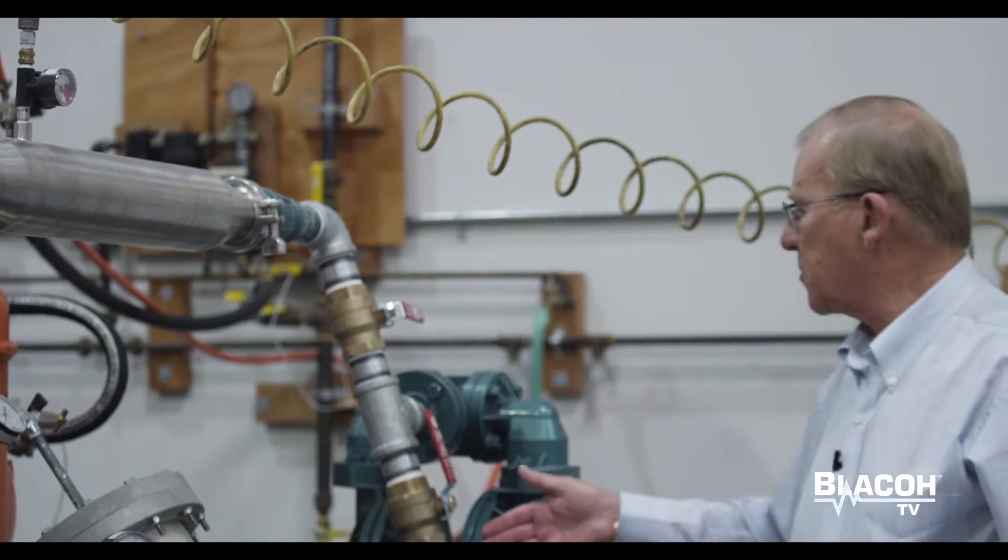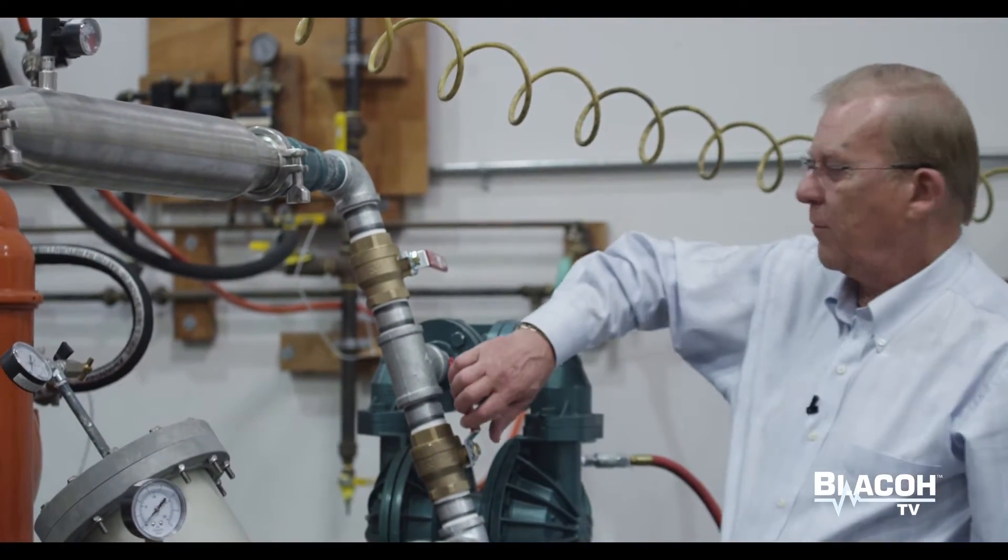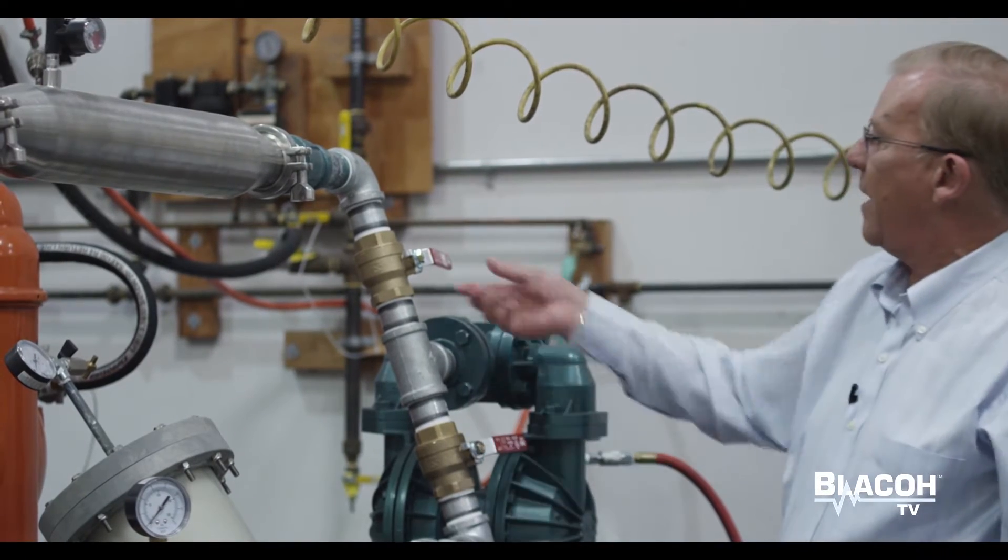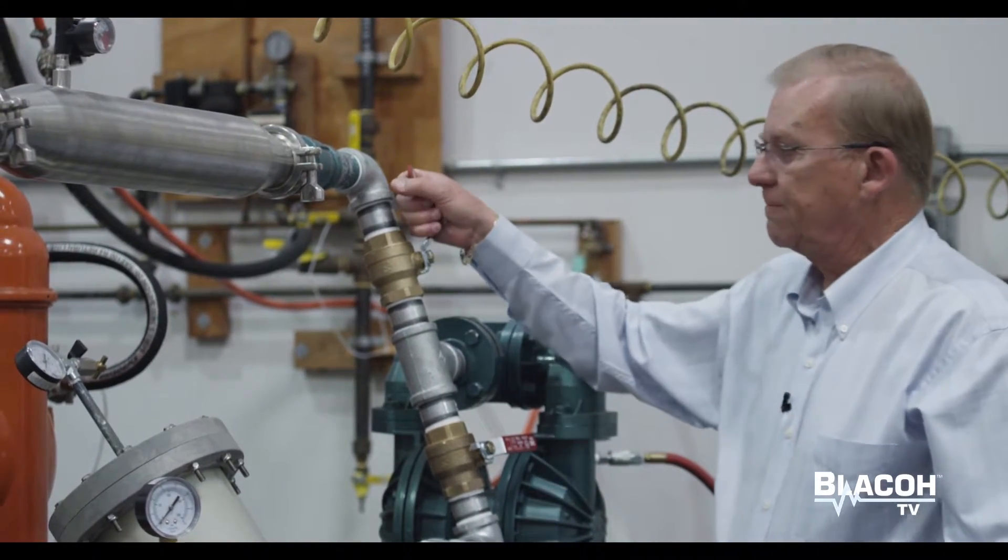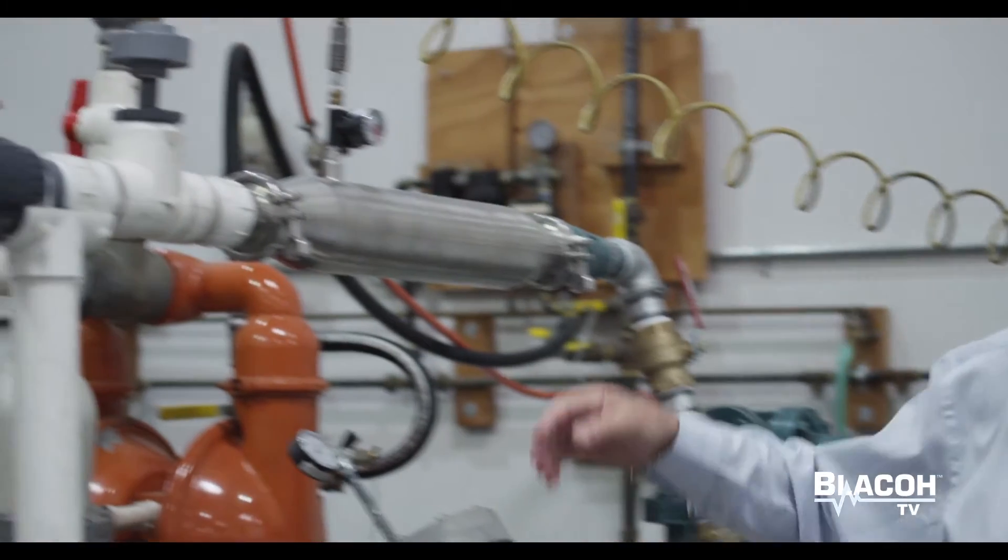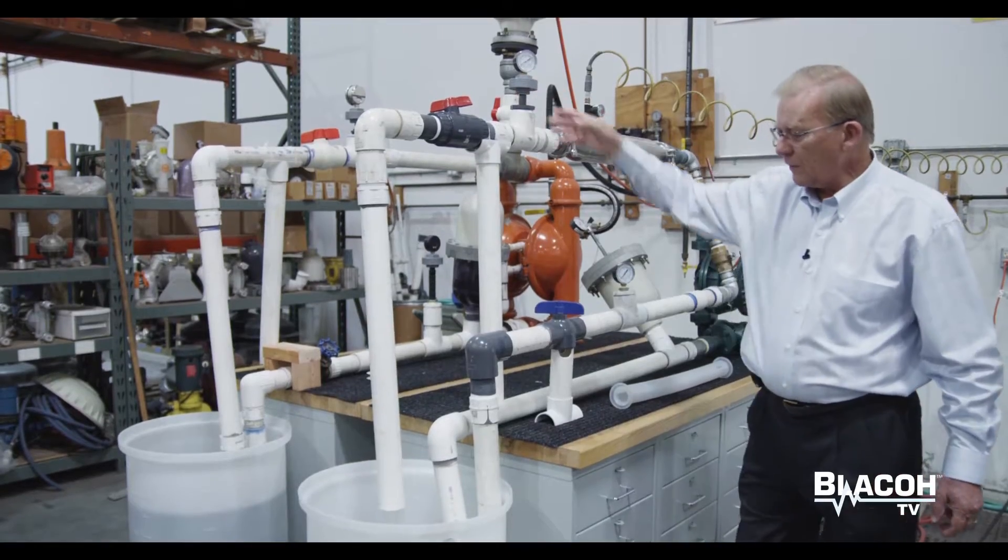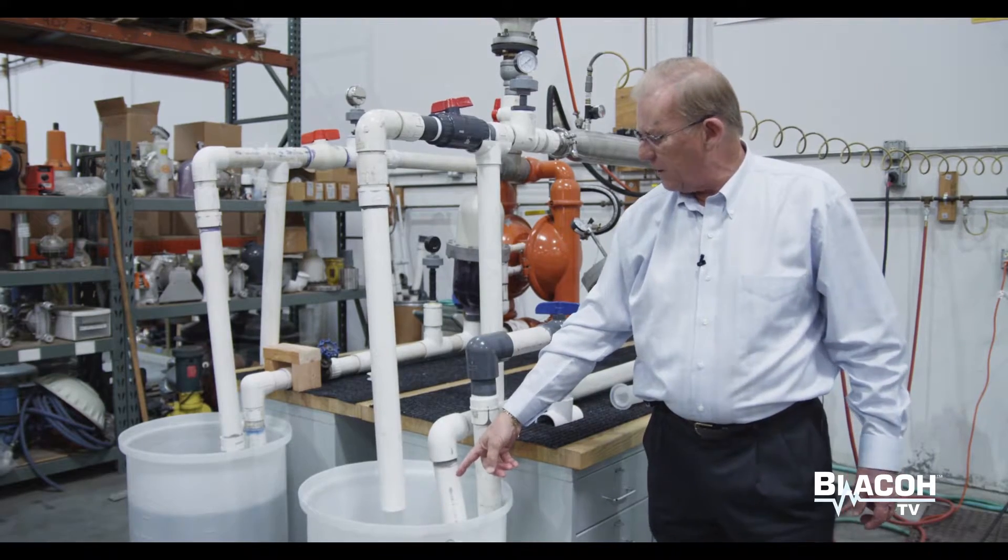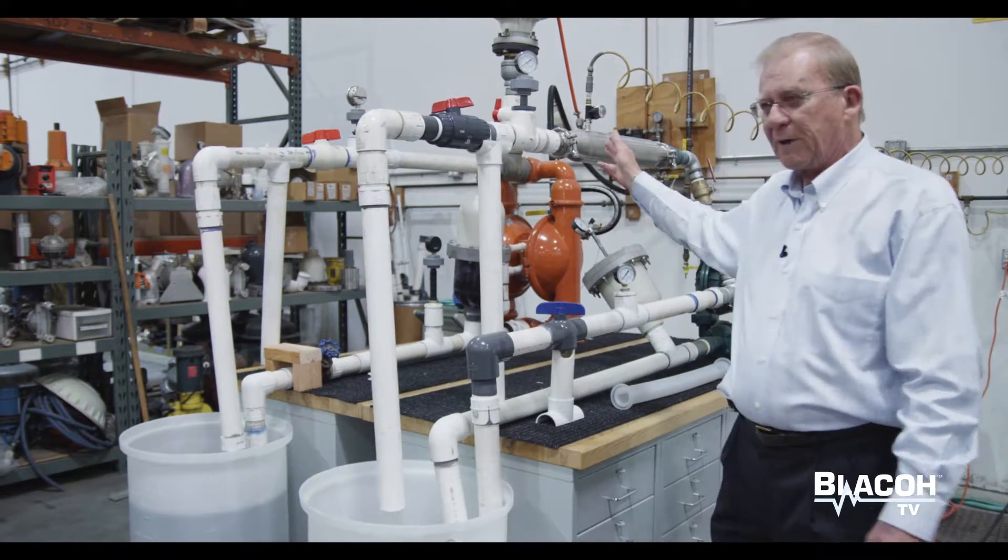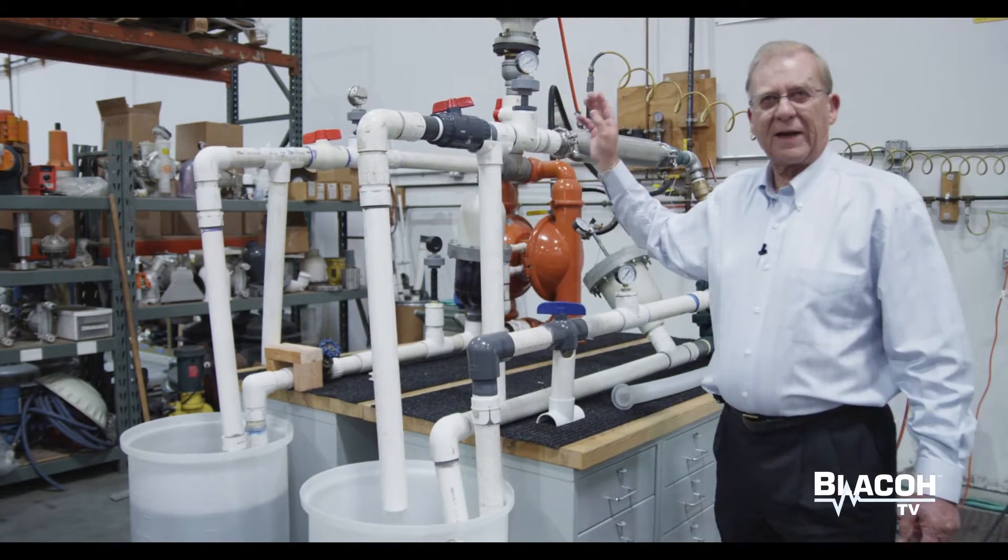So now I'm going to shift it from the non-dampened to the dampener side. And you'll see that the gauge is barely moving. The flow is near steady. We still have a little mechanical vibration, but that can be taken out with some flex couplings.